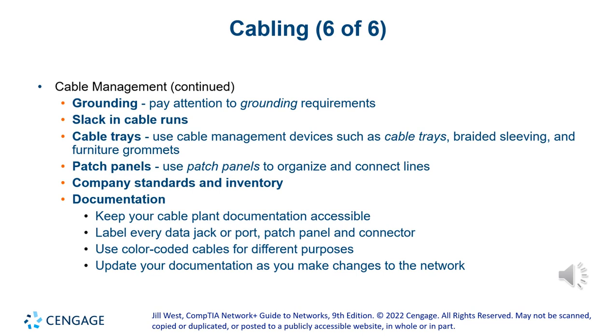And then that bend, remember, you cannot go beyond the bend radius, and make that connection. So you want to have everything organized. You can lay down J hooks, that is like a J that screws into a beam or something, so it will hold the cables. You want to have those about 1 or 2 feet apart, so the cable doesn't slack and start touching the drop ceiling, so they won't get tangled up with anything else and get damaged. So either have J hooks or the cable trays.